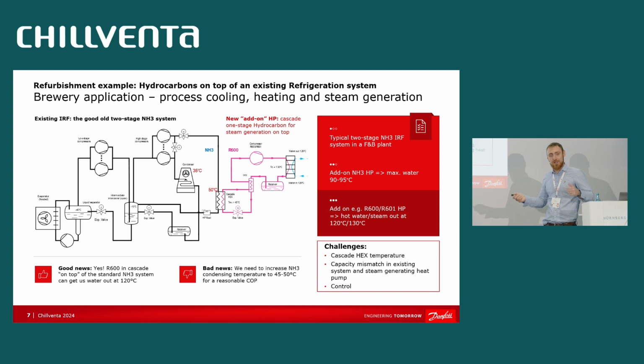So this will have a penalty on the ammonia system, but you need to make it also in a smart way, as you don't need all of the compressors of the ammonia side to lift to the higher pressure, I would say 50 C. You need maybe one. You need to account for load balancing. This is the second challenge. You may have several megawatts waste heat from the ammonia system, but you don't need several megawatts process steam generation for your production, right?